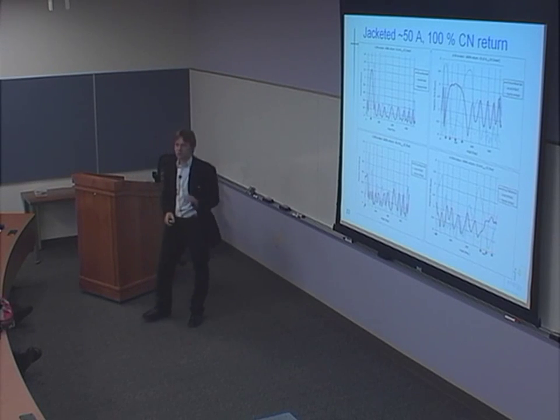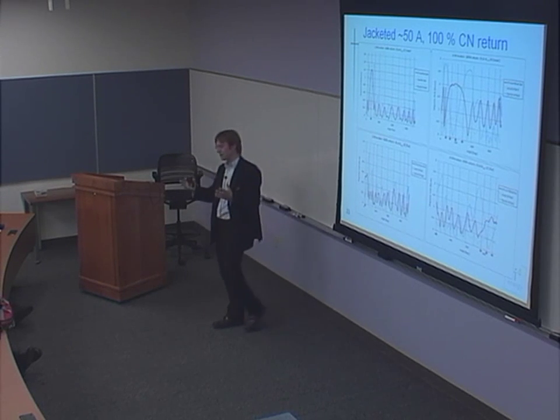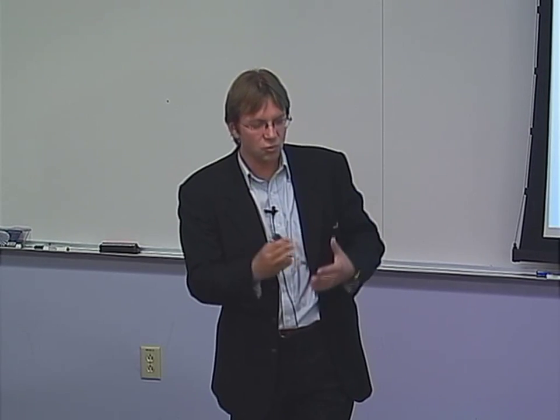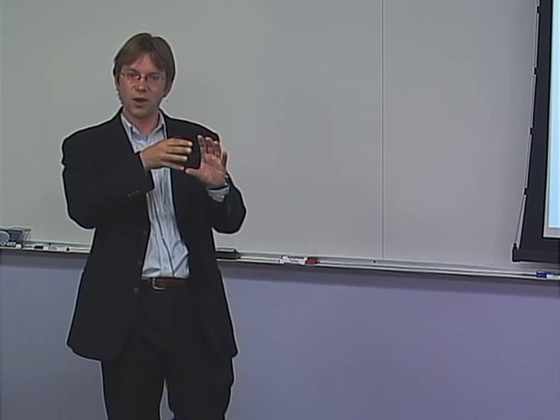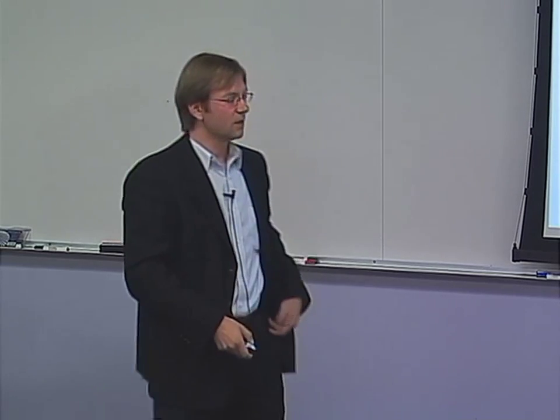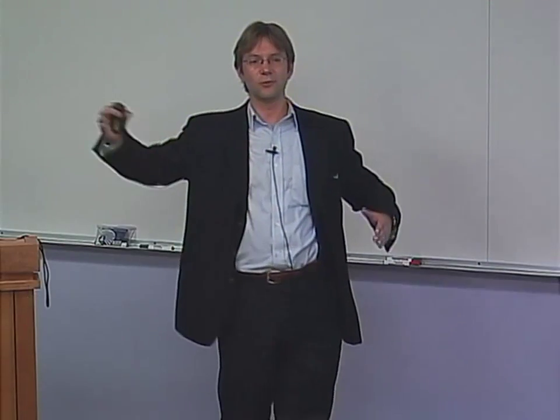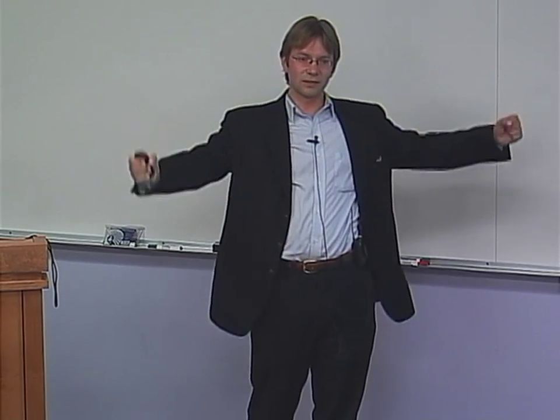However, there is a semiconductive shield around the cable as well, to essentially smooth out the electric field around the concentric neutral wires. And so there is some re-entrance of the current through that conductive shield. So you can see there is this, this is a little bit maybe bad, but you see this peak here. That's actually a CN that's not there, right? That has a break, but some of the current is still flowing. But you can still see that signature right here.